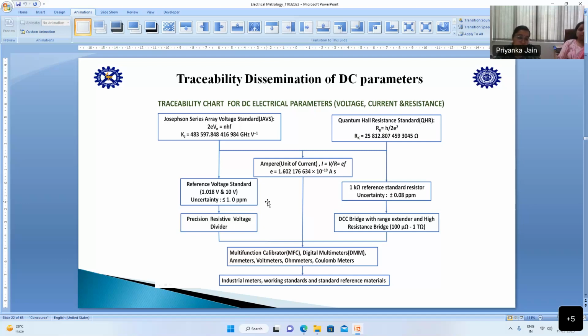From the Josephson voltage array standard, we take the traceability of the reference voltage standard, that is the Zener. Using Zeners and a 1 kilo ohm reference standard, which is calibrated against QHR, we calibrate all the resistance standards using the ratio method. That is 100 micro-ohm to 1 tera-ohm, and we establish traceability using a DCC bridge. By using precision voltage divider ratios 1:100 and 1:1000, we derive the traceability for 10 microvolt to 1000 volt. Based on this, we calibrate multifunction calibrators, DMMs, ammeters, and voltmeters of various ranges, and we provide traceability to industrial meters, working standards, and standard reference materials.